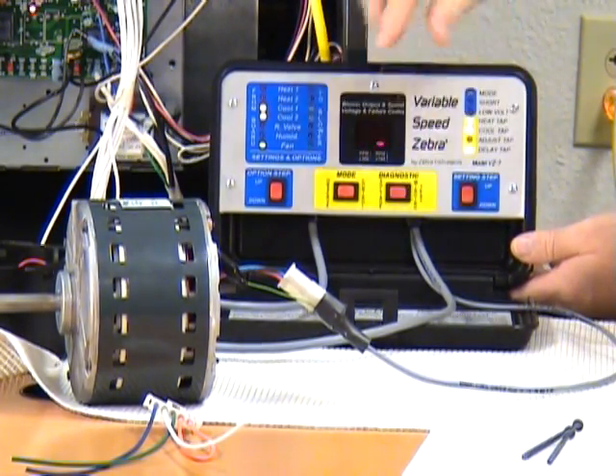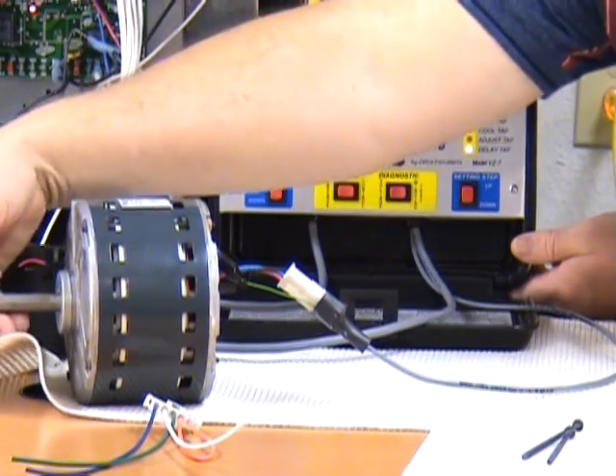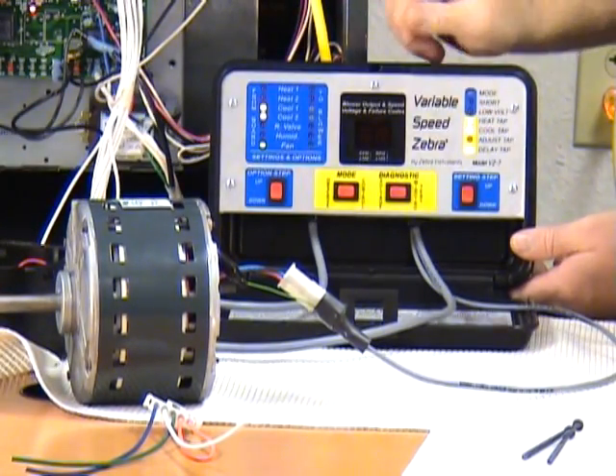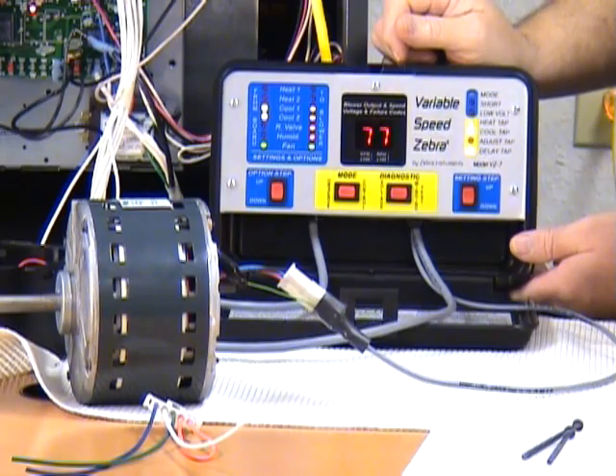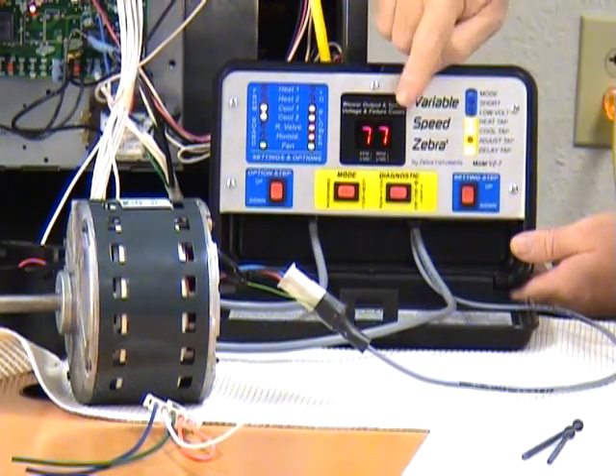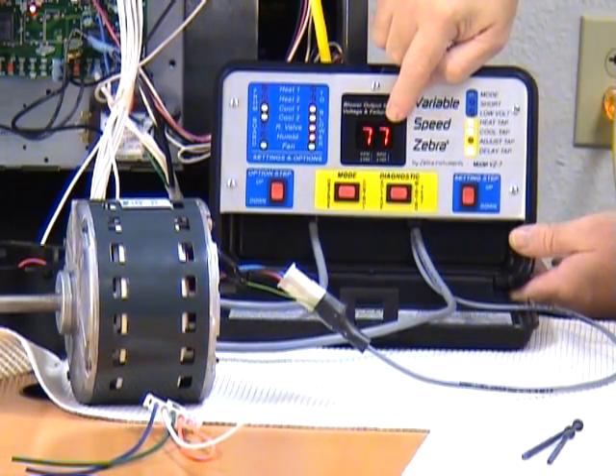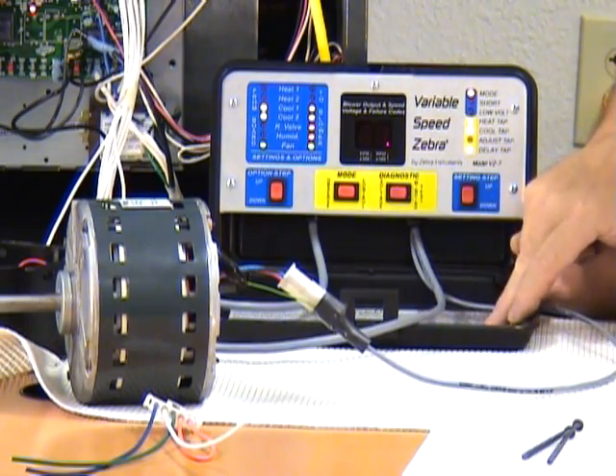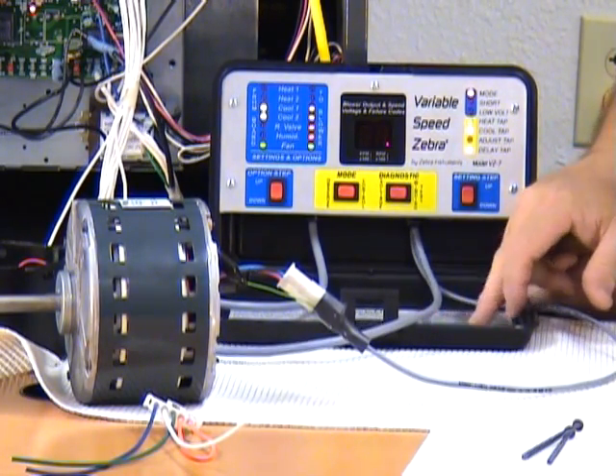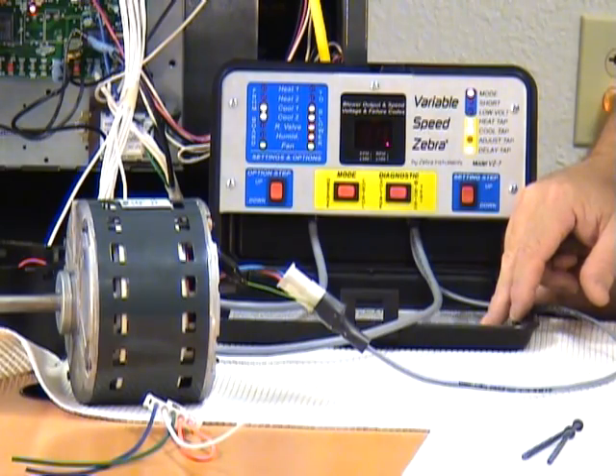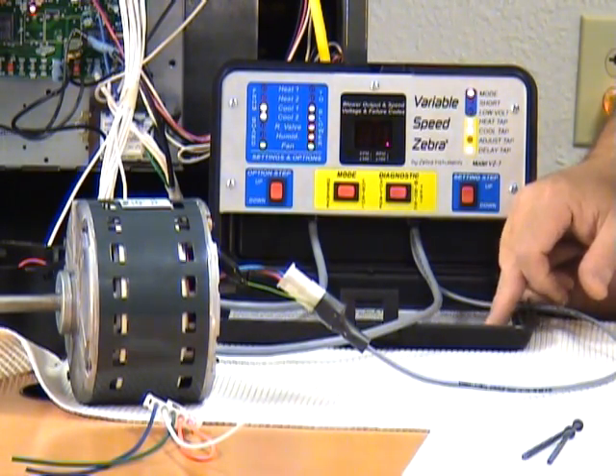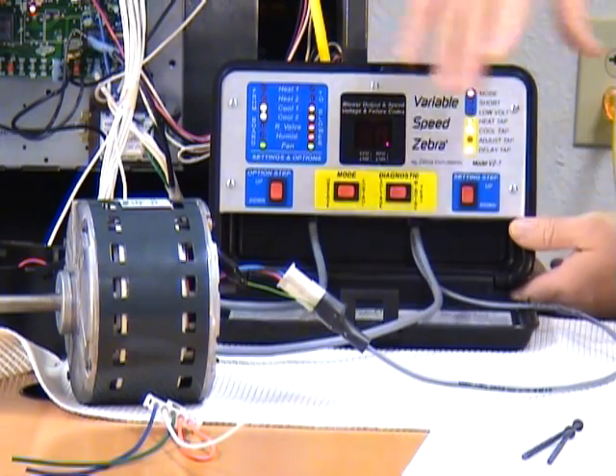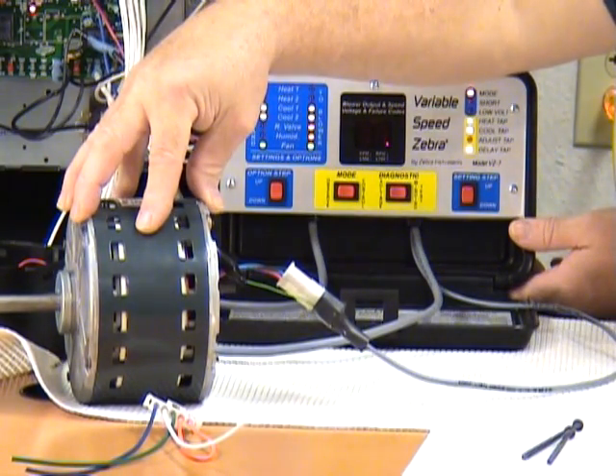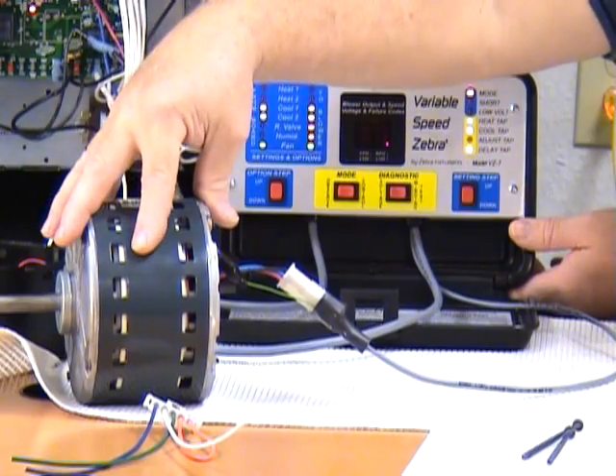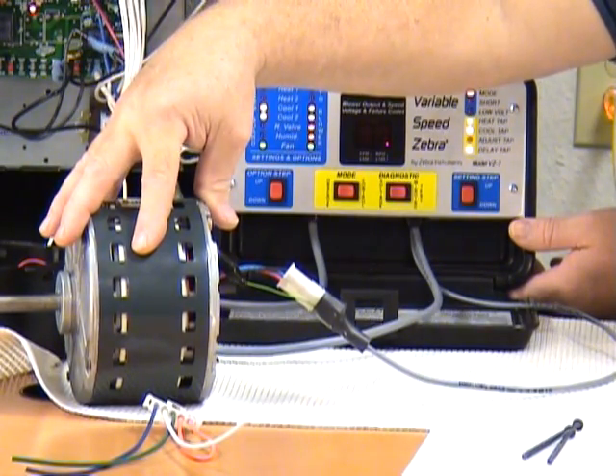So you press the winding test, you see the little thing chasing it, you spin the shaft once or twice. 3 or 4 seconds after that, it's done its test. In this case, it displays a 7-7. On the inside lid of your variable speed zebra, there's a dozen codes listed down there that tells you what those codes mean. A 7-7 means all clear, all tests okay. So the winding section of this motor has no problems in it found.